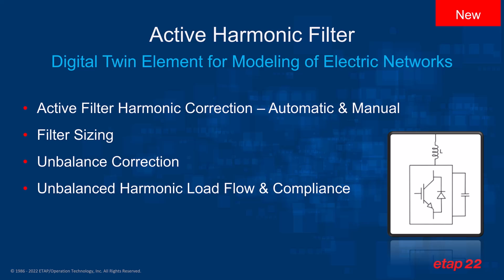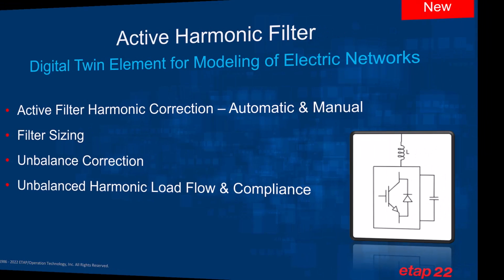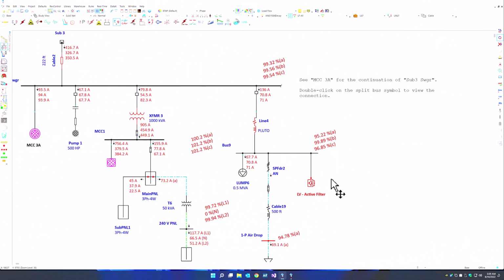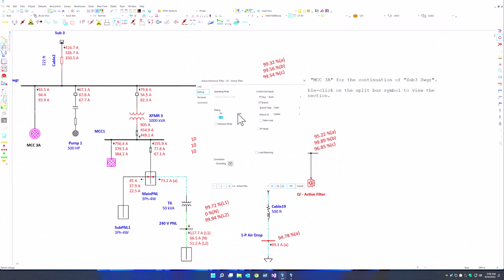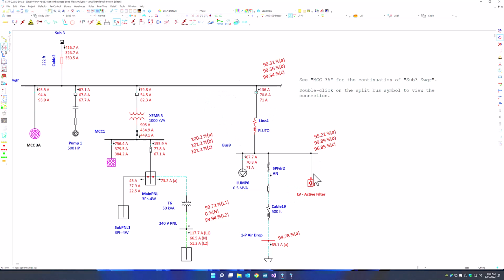Let's just take a look at active harmonic filter as it's operating for balancing or correcting the unbalance in the network. We have our active filter component that we can double click, bring up its various properties, and essentially connect it as a shunt component within the one-line diagram. When you run an unbalanced power flow, we can see the per phase flow, ABC flow, and we can clearly see there is unbalance on cable 2 as well as the transmission line.